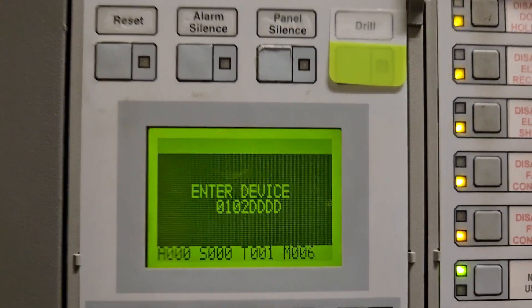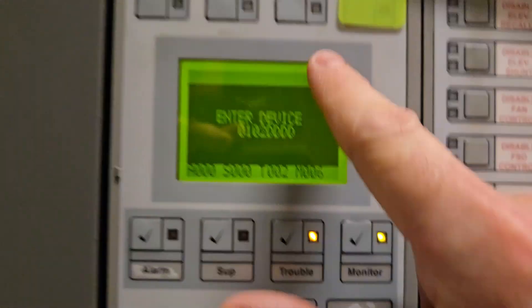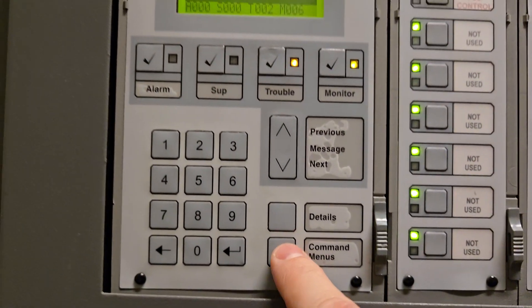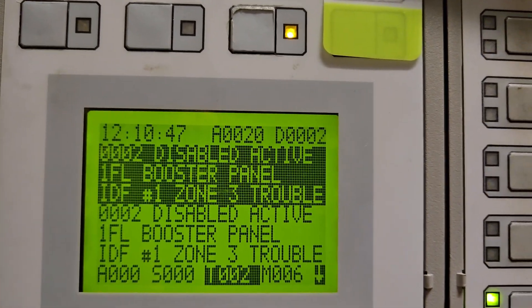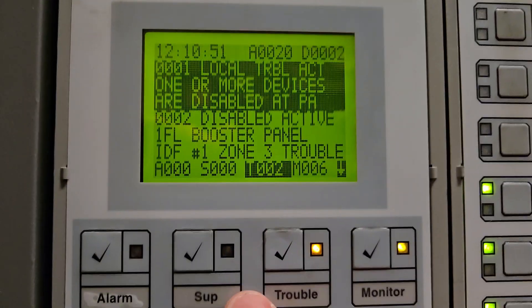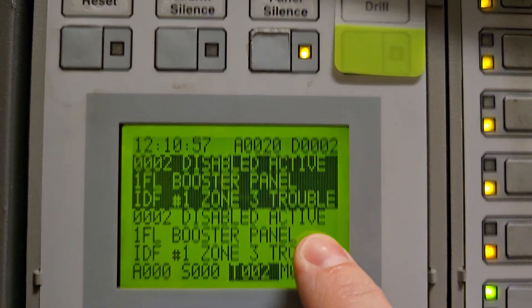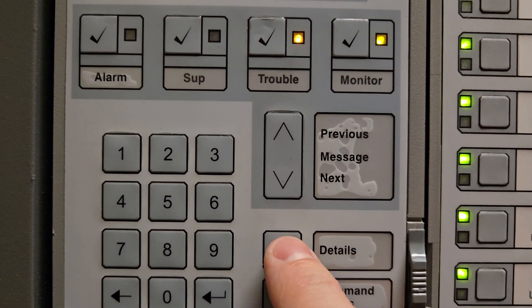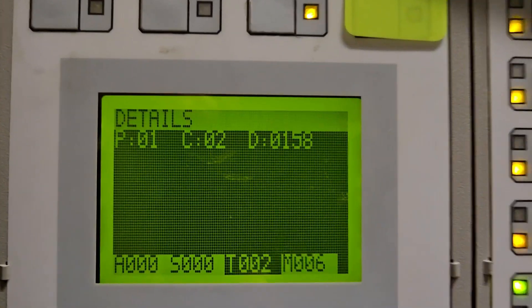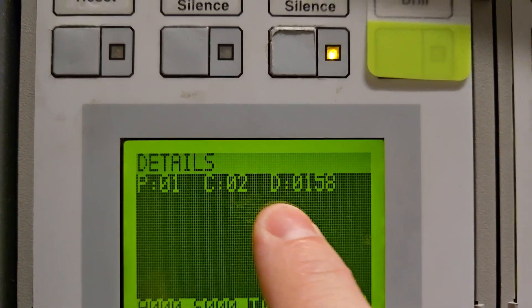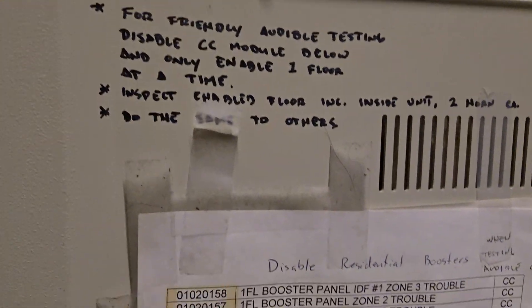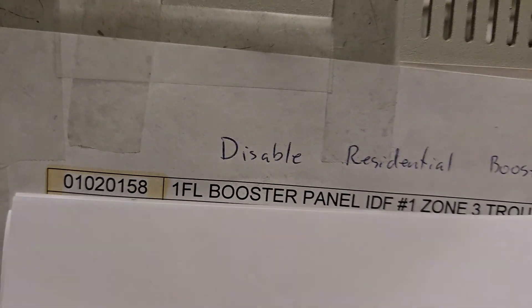I hit enter — the half arrow. The panel now indicates I have a new trouble, so I'm going to hit panel silence. I'll hit the command menu to go out, then the trouble button. I can see my original trouble, and then I hit the trouble button again and I have 'first floor booster panel IDF number one zone three trouble.' I'll hit the details button — right above the command menu — and it shows me that eight-digit number: 01-02-0158. That matches the first entry on my list: first floor booster panel IDF one zone three.